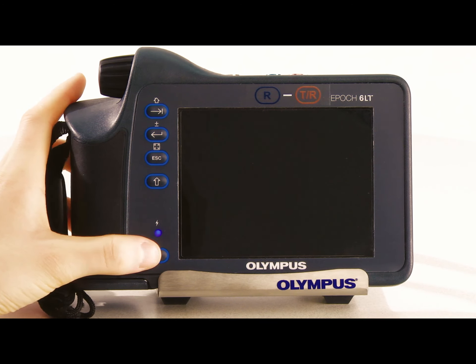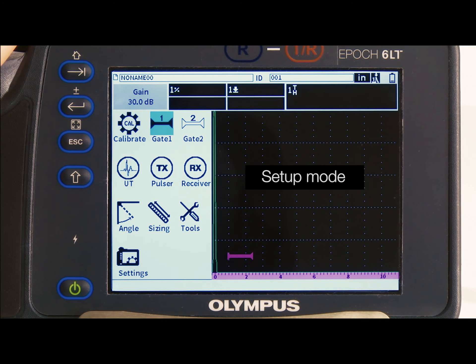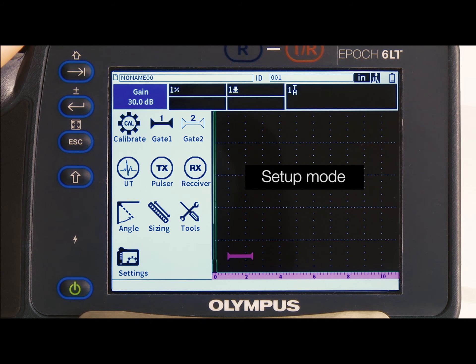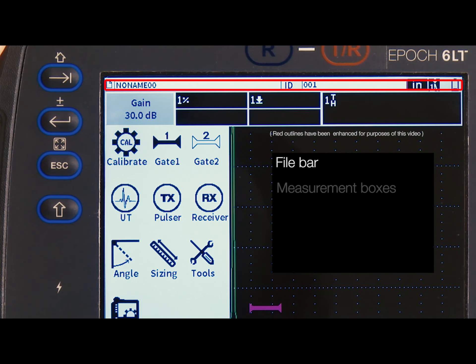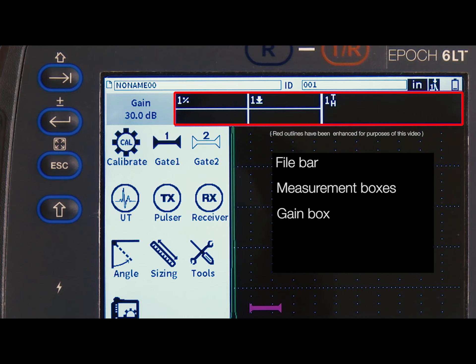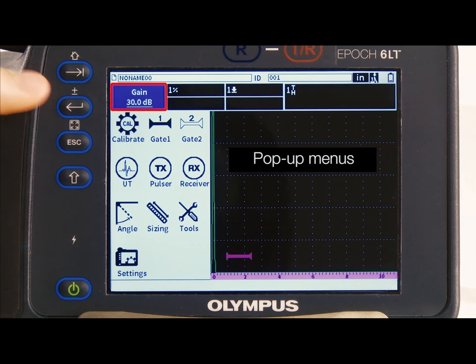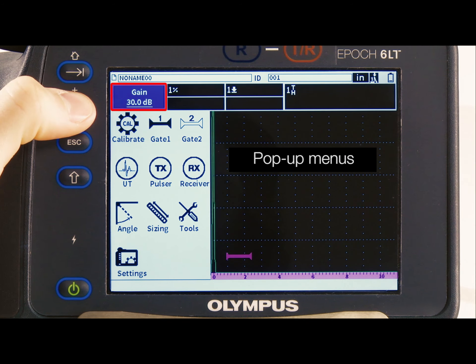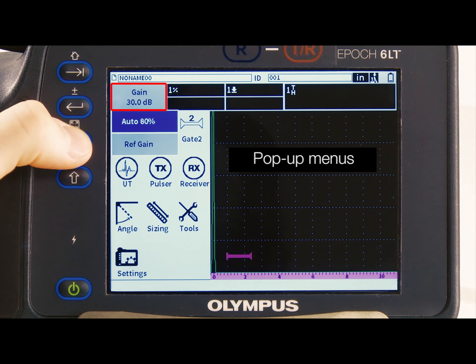When the instrument is powered on, there will be a split screen with icons on the left side, indicating that the instrument is in setup mode. Setup mode consists of the icon menu and several selectable groups, such as the file bar, measurement boxes, and gain box. Pressing the tab key will cycle through each of these groups. Additionally, each group has a pop-up menu, which can be accessed by pressing enter while that group is active and outlined in red.